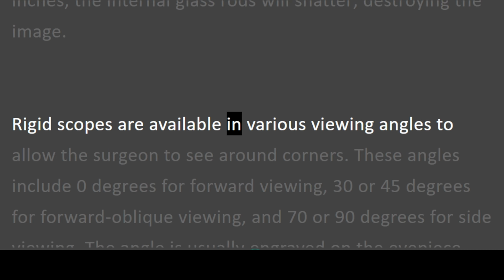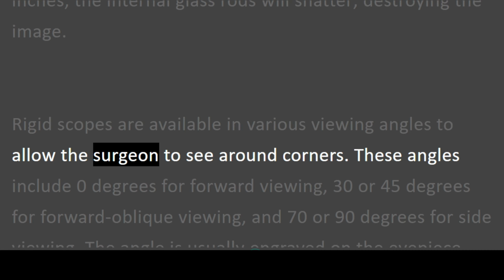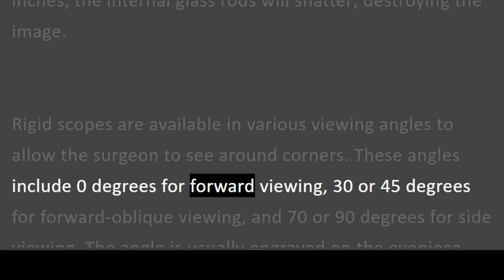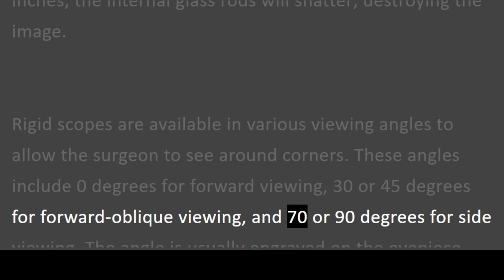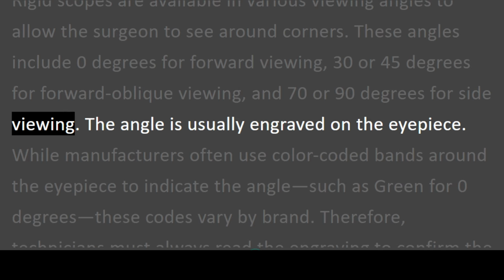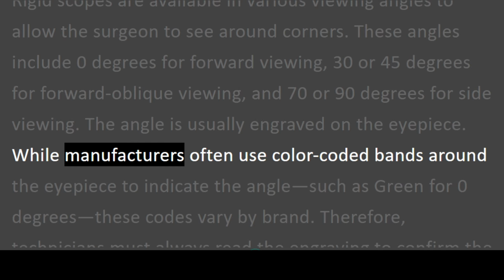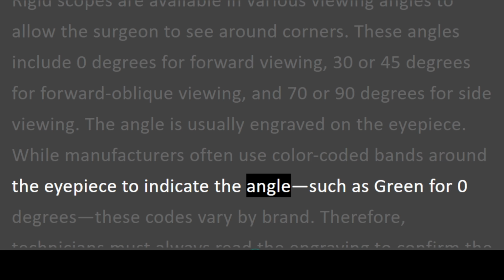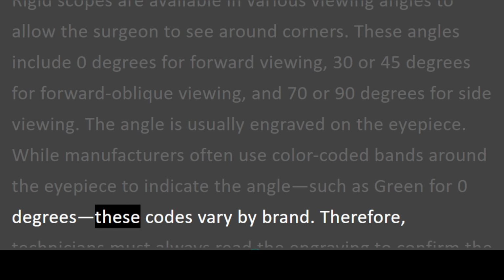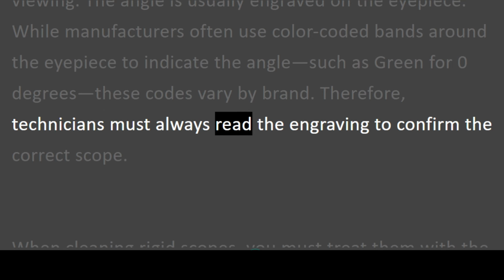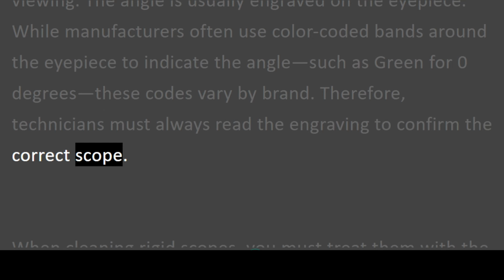Rigid scopes are available in various viewing angles to allow the surgeon to see around corners. These angles include 0 degrees for forward viewing, 30 or 45 degrees for forward oblique viewing, and 70 or 90 degrees for side viewing. The angle is usually engraved on the eyepiece. While manufacturers often use color-coded bands around the eyepiece to indicate the angle, such as green for 0 degrees, these codes vary by brand. Therefore, technicians must always read the engraving to confirm the correct scope.